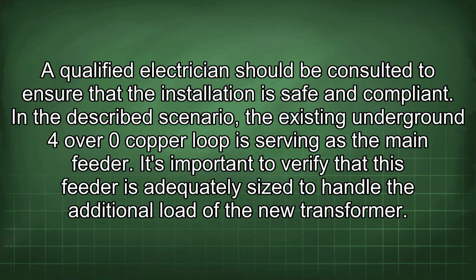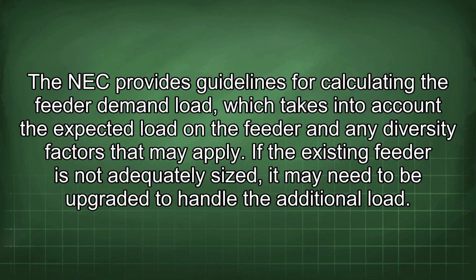In the described scenario, the existing underground 4/0 copper loop is serving as the main feeder. It's important to verify that this feeder is adequately sized to handle the additional load of the new transformer. The NEC provides guidelines for calculating the feeder demand load, which takes into account the expected load in the feeder and any diversity factors that may apply. If the existing feeder is not adequately sized, it may need to be upgraded to handle the additional load.